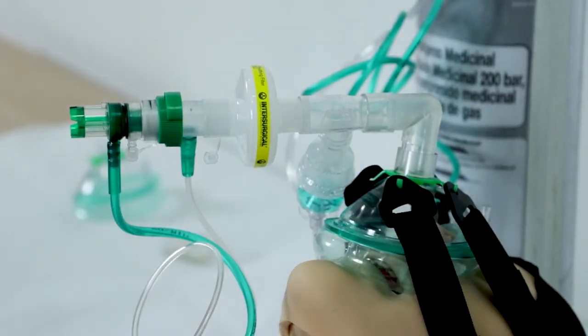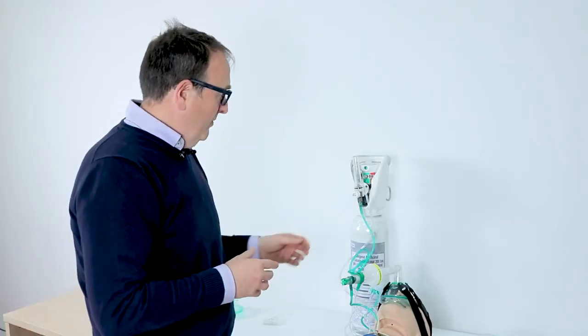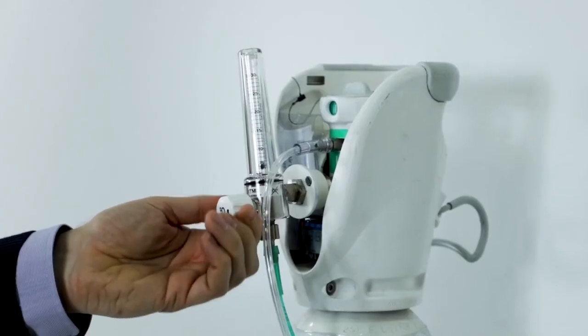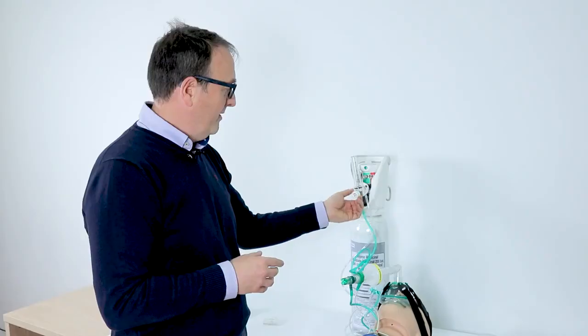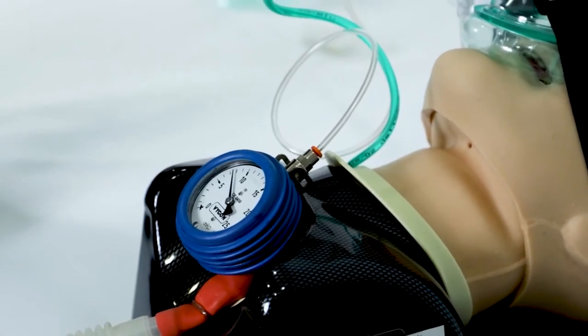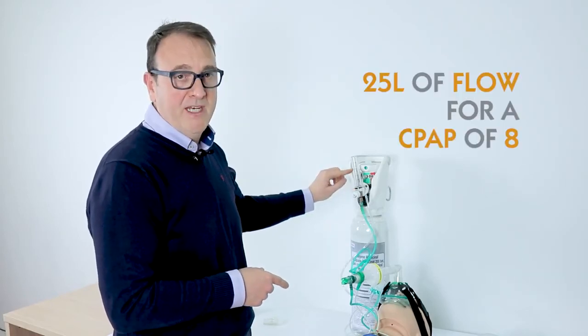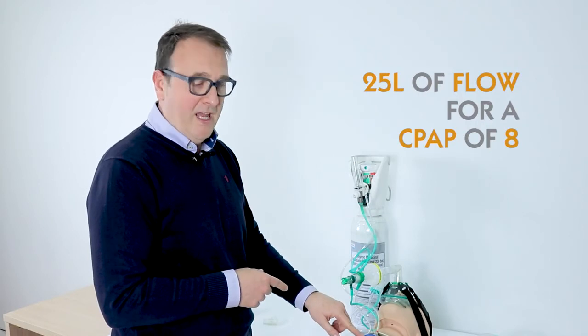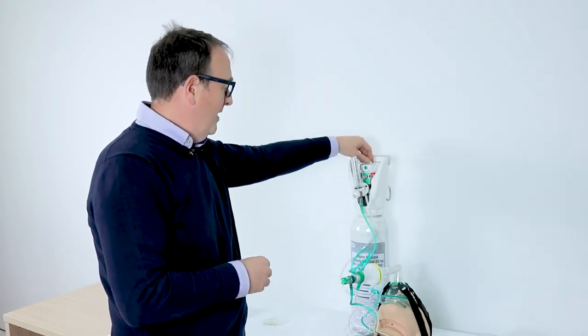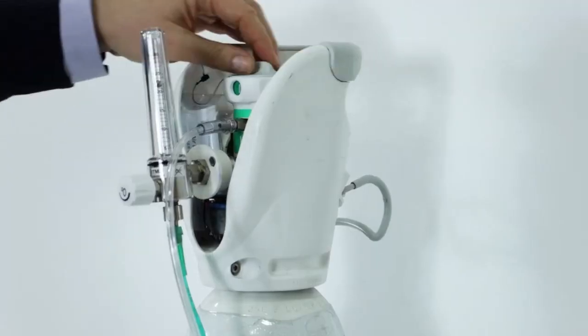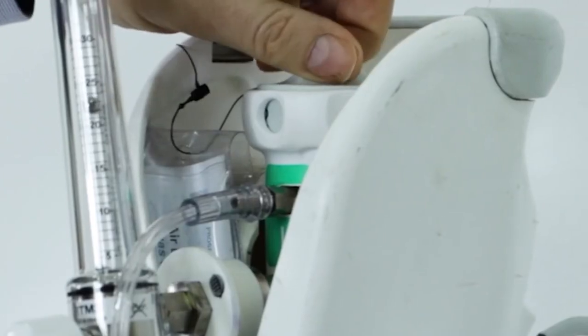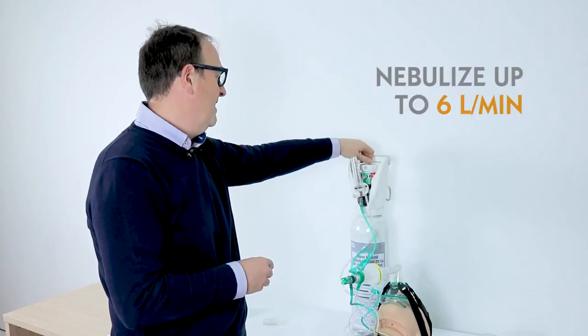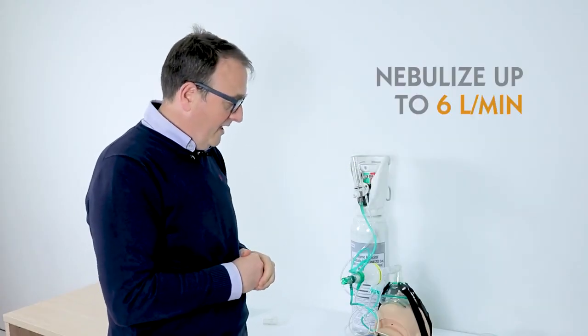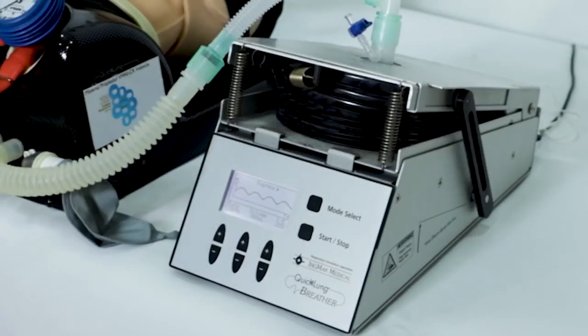And finally, to finish this video, I'm going to show you how to interconnect the T-piece for nebulizing therapy in a lung model. First of all, we need to start with the CPAP. So we have to increase progressively the flow until the desired pressure. For example, 25 liters per minute to achieve a pressure of 8. Secondly, we have to connect the system to the oxygen of the nebulizer and increase the flow up to approximately 6 liters. Okay, and I'm going to start the simulator.